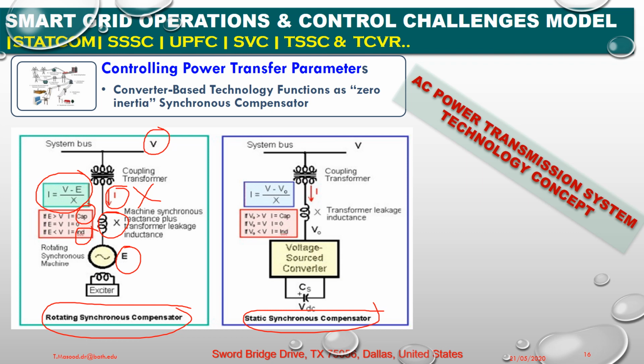Similarly, in the static synchronous compensator, this is my transmission line voltage V and this is my converter output voltage V0. This is my I, as we have shown in the rotating compensator. This is how we calculate I: V minus V0 divided by X. If V0 is greater than V, then I will flow in capacitive mode of operation. If V0 is less than V, then it will be inductive mode of operation. If V0 is equal to V, then there will be no flow of current. This is the transformer leakage inductance. So this is the static synchronous compensator, and this is how they operate in parallel to each other.